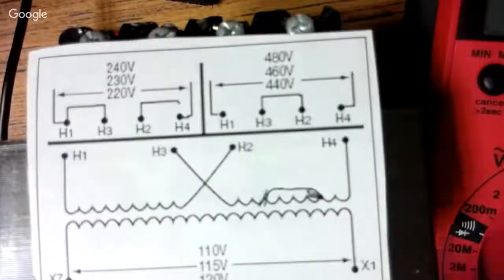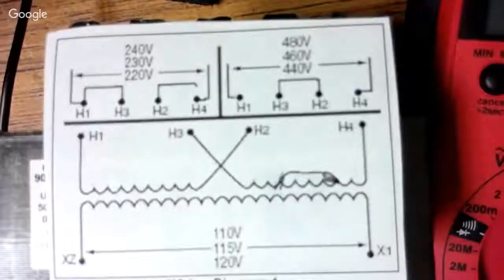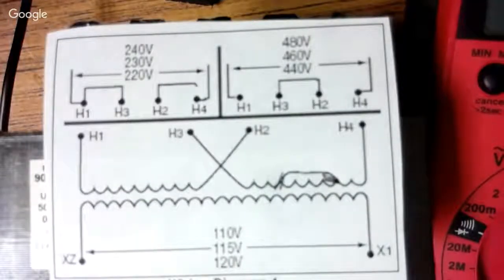So that would be a pretty good lesson. Most of your transformers you see are going to be in this dual voltage configuration, so pay particular attention to that when hooking it up. If you hook it up incorrectly, you will blow up stuff. All right? If you hook 220 to a 480, you're not going to get the right voltage, and whatever's coming out is going to be incorrect. So even if you hook it up wrong, that's fine. Just don't have anything connected to the secondary. So have it, and you can check the voltage on the secondary before applying it to the rest of the circuit.